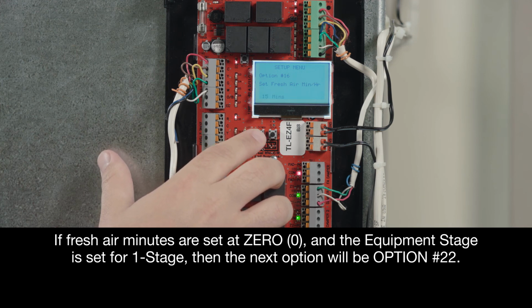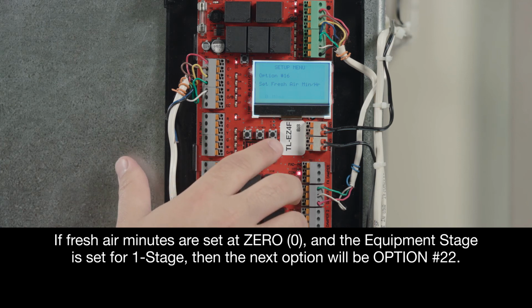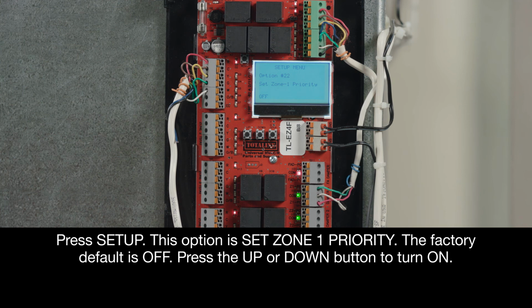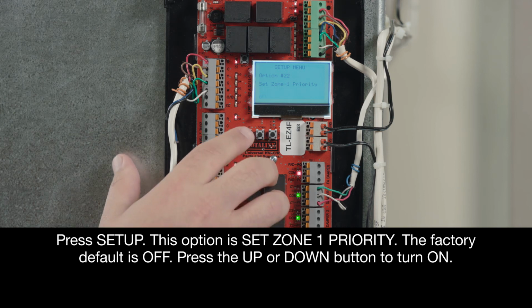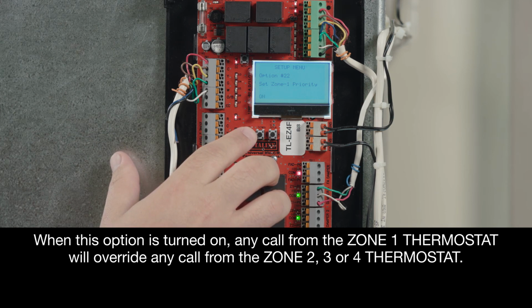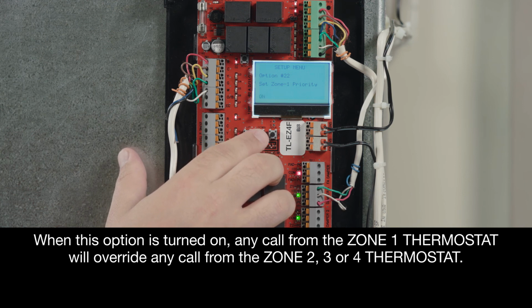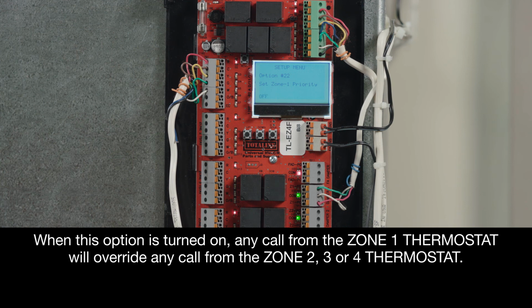If fresh air minutes are set at 0 and the equipment stage is set for 1 stage, then the next option will be option number 22. So press Setup to get there. This option is Set Zone 1 Priority. The factory default is off. Press the up or down button to turn on. When this option is turned on, any call from the Zone 1 thermostat will override any call from the Zone 2, 3, or 4 thermostat.